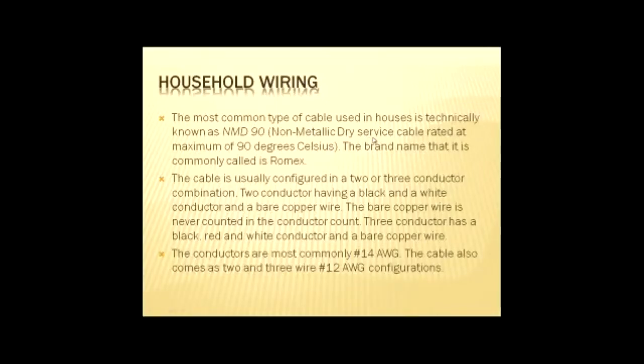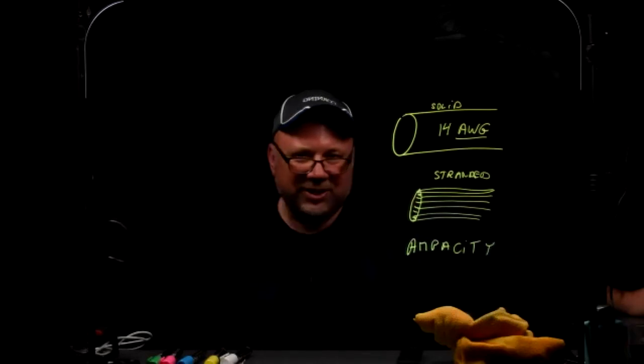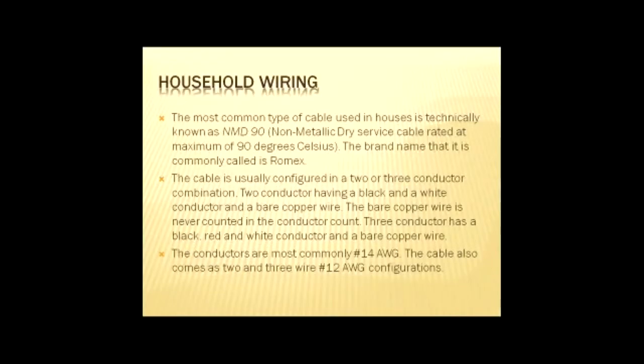Service cable. Service means that it is supposed to supply the power. It's not a communications cable, like a microphone cable or speaker cable that's supposed to carry signal. A service cable is supposed to provide you power. Service cable rated at maximum of 90 degrees Celsius. It's supposed to withstand 90 degrees. Water boils at 100 degrees Celsius. So this thing is supposed to handle 90 degrees Celsius. So NMD90 stands for non-metallic dry service cable rated at maximum 90 degrees Celsius.